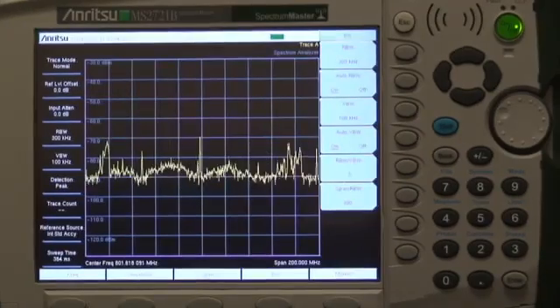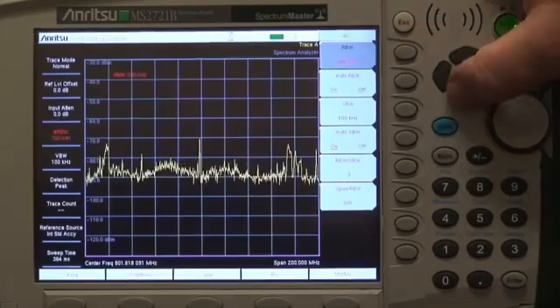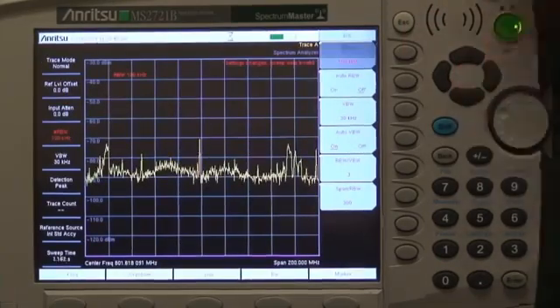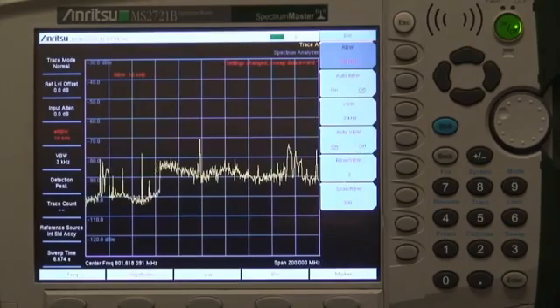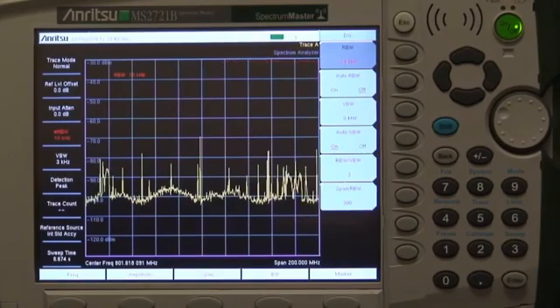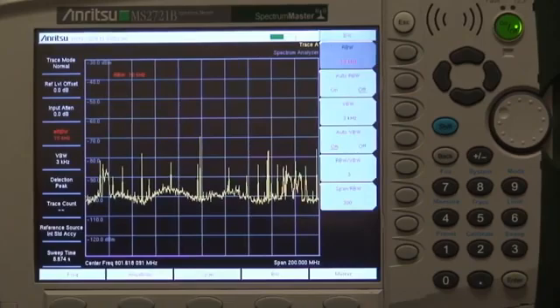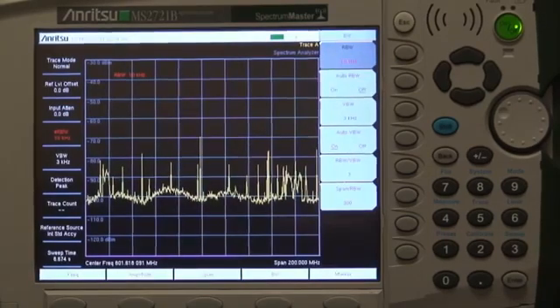You can use a wide RBW to get fast measurements at the expense of higher received noise and reduced frequency resolution, or you can use a narrower RBW with slower sweeps to reduce noise, get better frequency resolution, and increase sensitivity. Because you have the freedom to set the resolution bandwidth from 3 megahertz all the way down to 1 hertz, you can make the trade-off that makes sense for your measurement.